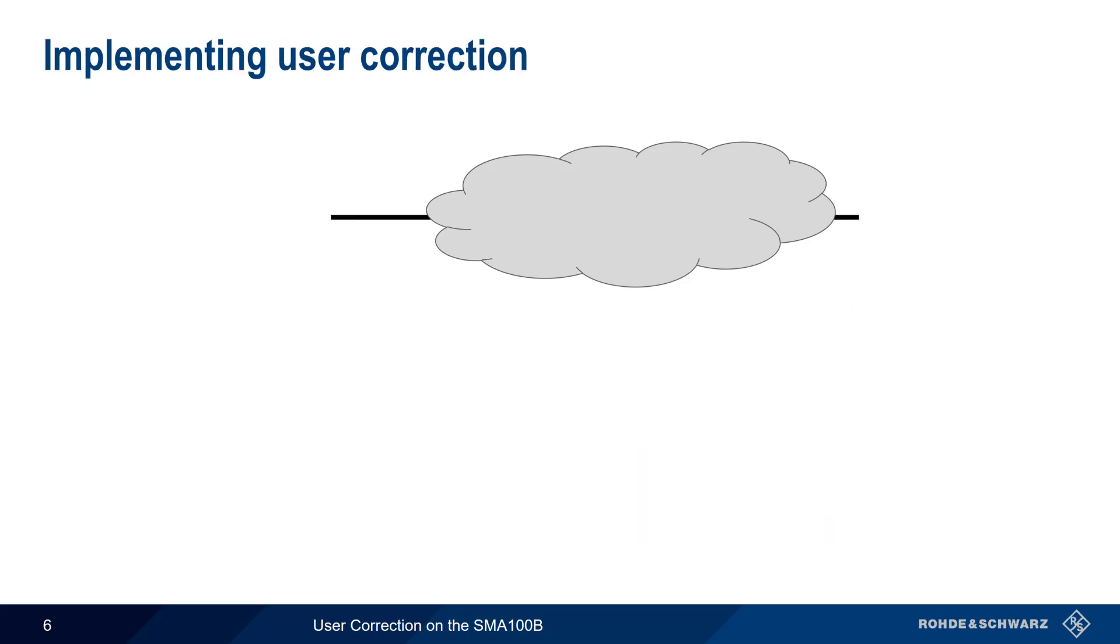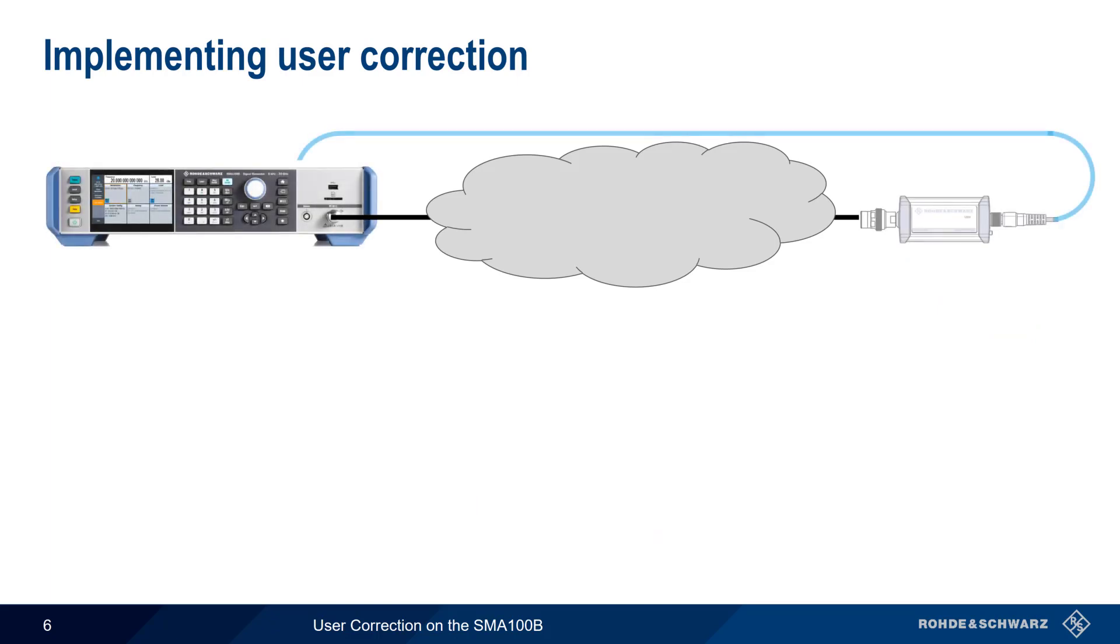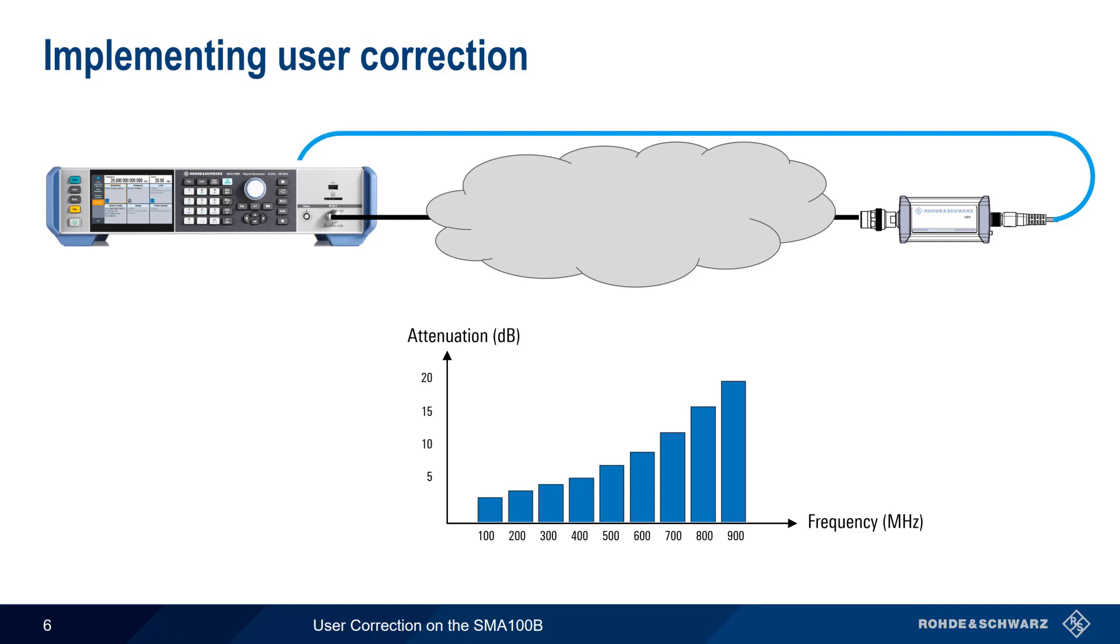The most common way that user correction is implemented is by using a signal generator and a power sensor to measure the frequency response of the signal path, and then use those values to create a correction table. This presentation will show how user correction tables are built and applied using an SMA100B analog signal generator and an NRP series RF power sensor.